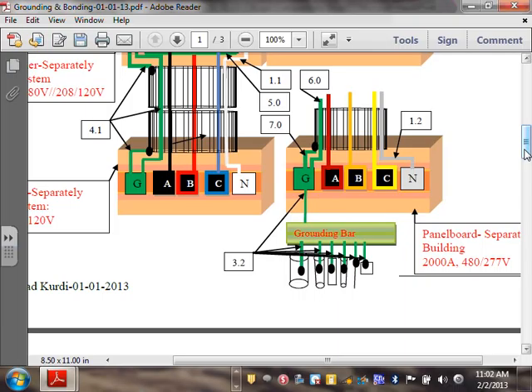Okay. Now, number one, you have to have a 5 conductor cable if you're going underground, buried cables. 5 conductor cable, or you have to have 5 conductors in a PVC conduit or rigid conduit, or you don't want to bury EMT. Rigid, treated for corrosion, or typically everybody knows the conduit of choice when we go underground is what? PVC, because of corrosion. Okay, so now, just because I am pulling rigid conduit here, I need to bond the conduit. So I'm pulling a rigid.